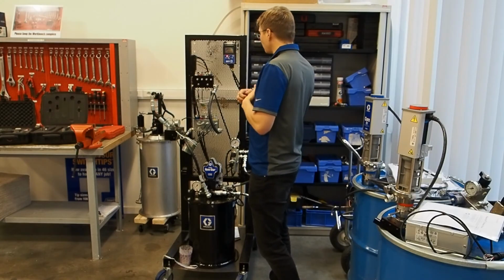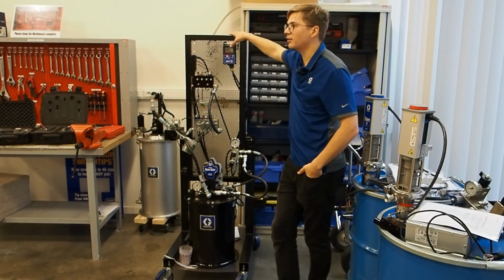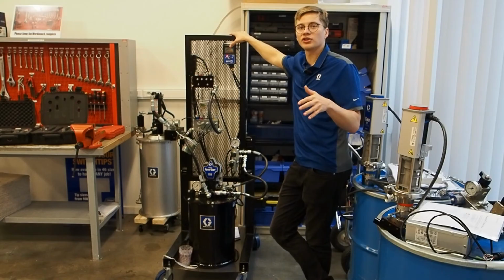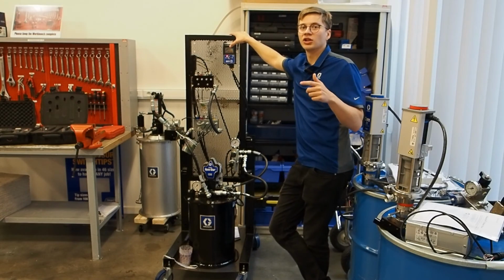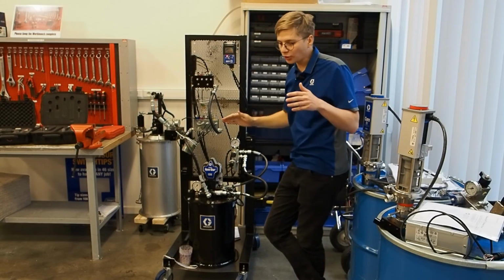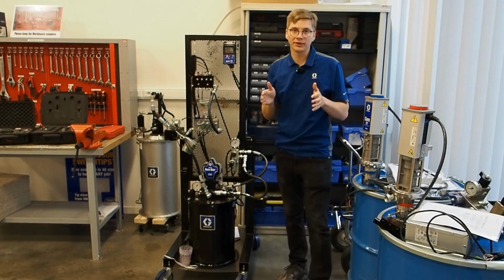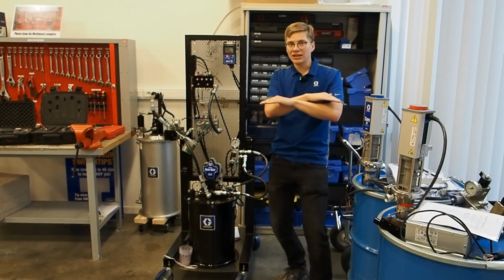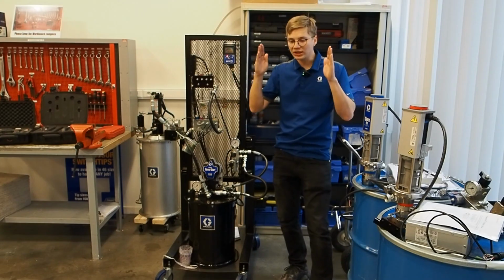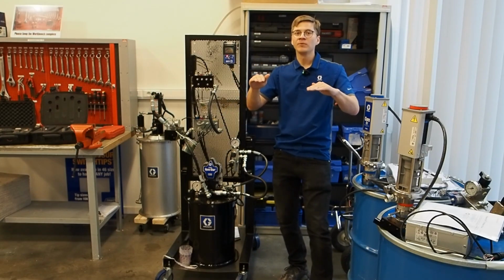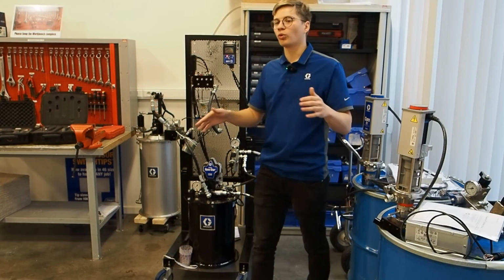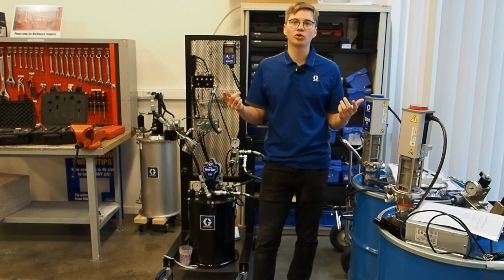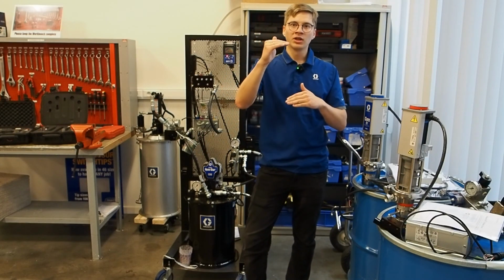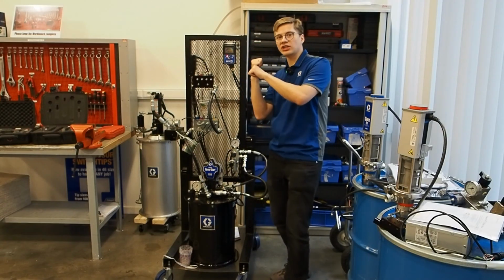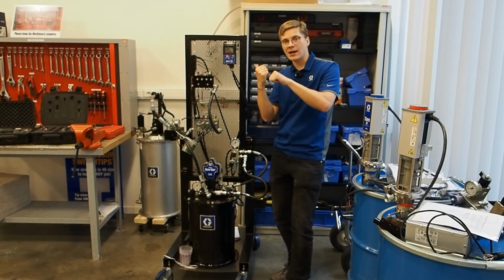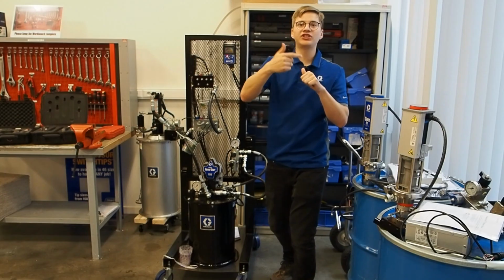Smart. But the interesting thing also is that this controller is not only time-based on and off, it's interval-based. So we tell the controller, I don't care how much time you spend on building up the pressure, just maintain a 1 hour interval. Just lubricate my machine every hour. So if today it's pretty warm weather, it's very nice, and it took 1 minute to build up pressure, then the controller will adjust the time off to 59 minutes.